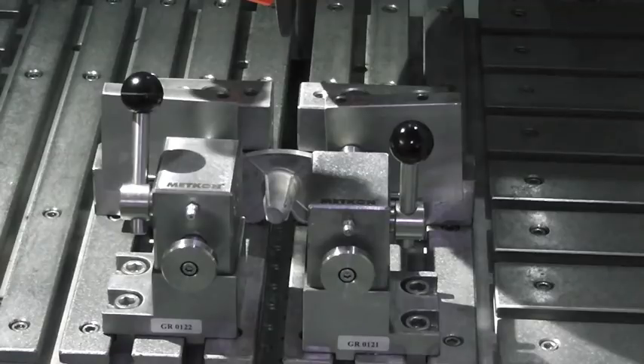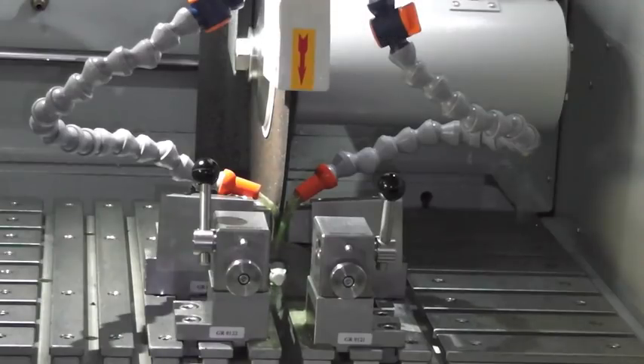This machine uses two quick acting vices, but there are many more vices available from Metkon to suit all sample shapes and sizes. The 80 litre recirculation tank is included with the machine and ensures samples are kept cool during cutting.